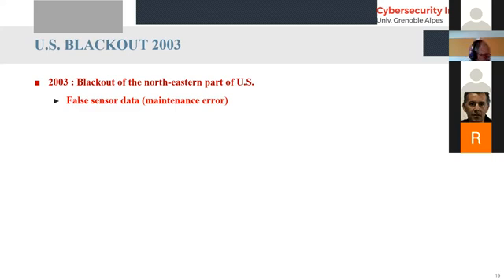The operator exchanged a sensor with output 0 to 1 ampere for one with output 0 to 5 amperes. That means for the same input, the output of the sensor was 5 times lower. He reconfigured the device but forgot to reset it, to restart it. So the PLC didn't take into account the modification. For the PLC, the data was still interpreted as coming from the other category of sensor.